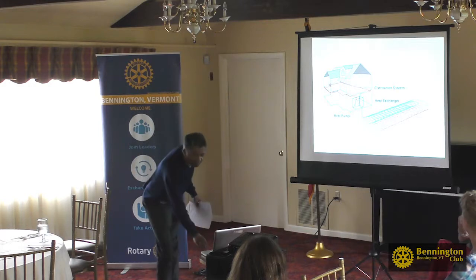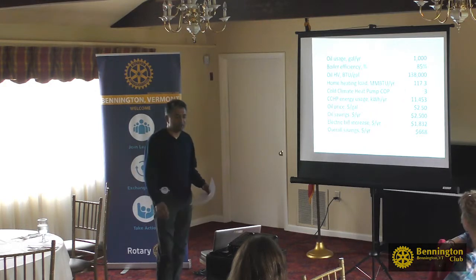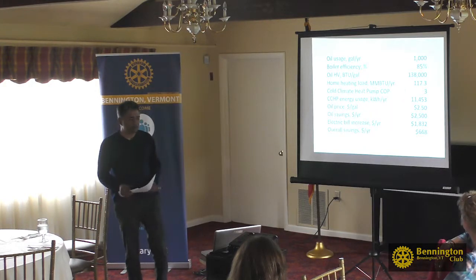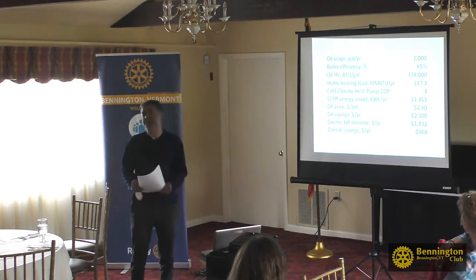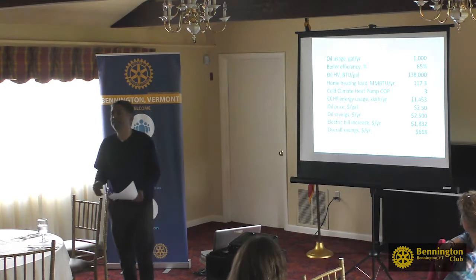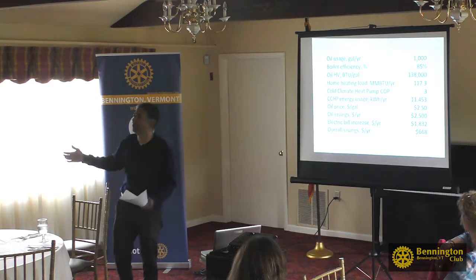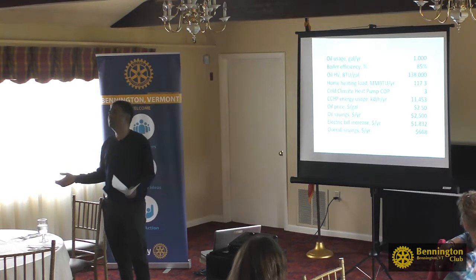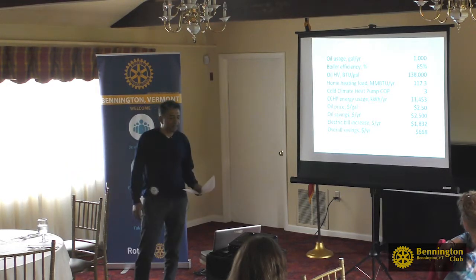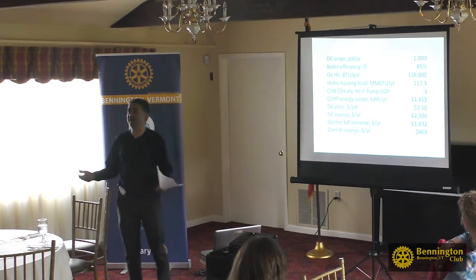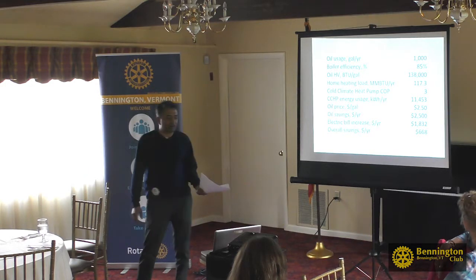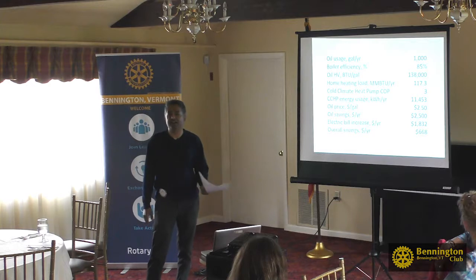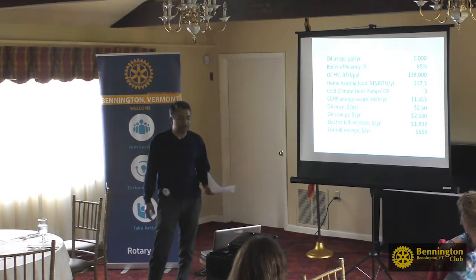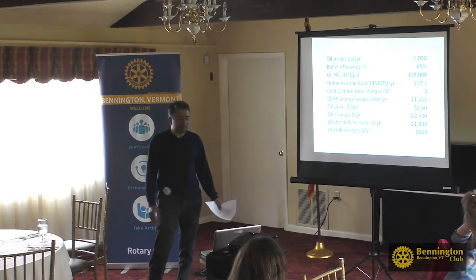All right, so I promised you that I'll show you what the calculations look like. Numbers. Okay, so let's say that you have a home which consumes 1,000 gallons of oil, right? And the boiler has an efficiency of about 85%. The oil's heating value is about 138,000 BTUs or so, right? So you can estimate, based on that, the home heating load is about 117 million BTUs a year.